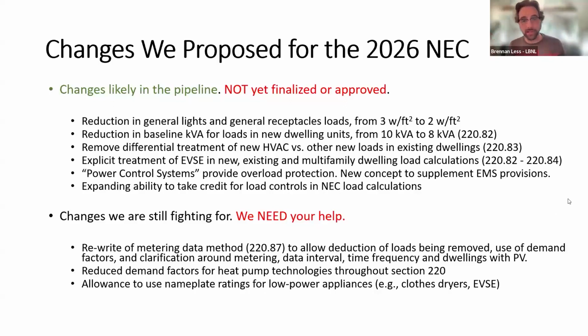We still need help reworking the metering data method 220.87. We're trying to make that friendlier to electrification, and trying to get reduced assumptions around heat pumps throughout the code, generally trying to get the code to let you use nameplate ratings rather than default values. I talked about EVSE, where you're forced to think about it as a 7 kilowatt load instead of what you're actually installing, which might be less than that.